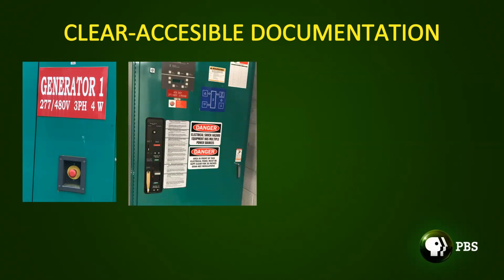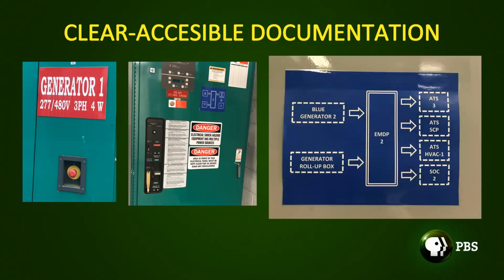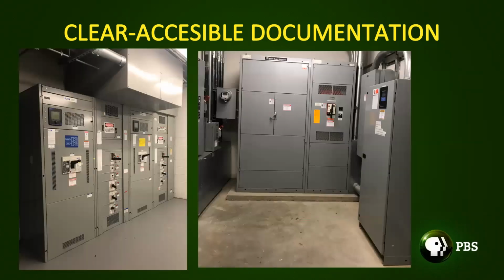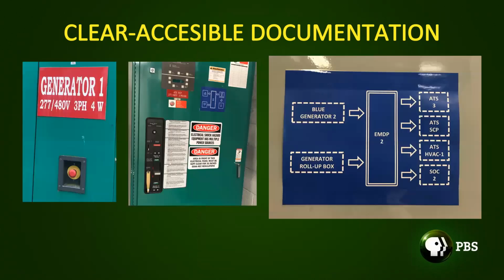Another example - this is one of our numerous automatic transfer switches. We actually have 7 of them that switch our load from commercial power to generator power. With that number, it's pretty easy to lose track of what they do. So this is what that little green square is for - it tells you absolutely that this switch is concerned with emergency power distribution panel 2. And what feeds emergency distribution panel 2? Generator number 2. That's what feeds it.